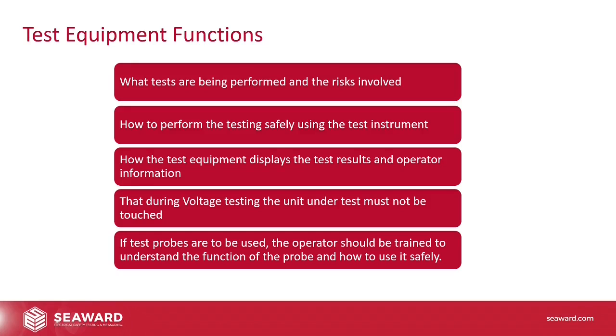And that during high voltage testing, the unit under test must not be touched. This is again a really big thing. It's really important. Do not touch the equipment under testing at all. Okay, even if you're isolated, even if you're wearing gloves, doesn't matter. Do not touch the equipment under test. If test probes are to be used, the operator should be trained to understand the function of the probe and how to use it safely. Again, using probes is really high on the list of things that should be considered for training, because they are near the equipment, they are near the danger, and it's important to know how to get through those tests safely.